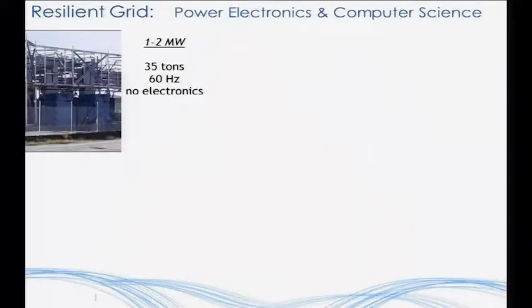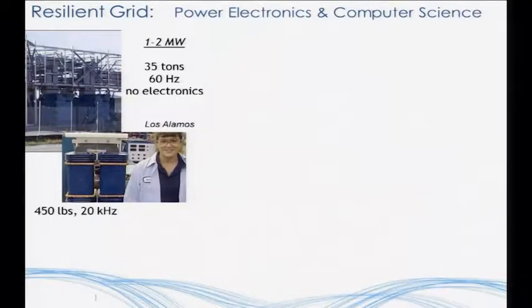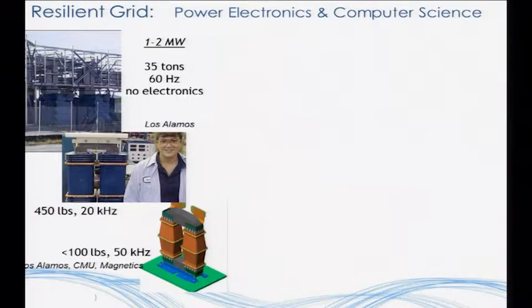So what's the impact of these systems? If we look at 1 to 2 megawatts, this is our picture of how the grid looks: 35 tons of magnetics working at 60 hertz, with almost no electronics inside. If you add power electronics, you can up the switching frequency to 20 kilohertz, and suddenly your magnetics get smaller, your transformer is 450 pounds. Go a little faster with better topology and new materials, and you can drop that down to 100 pounds.